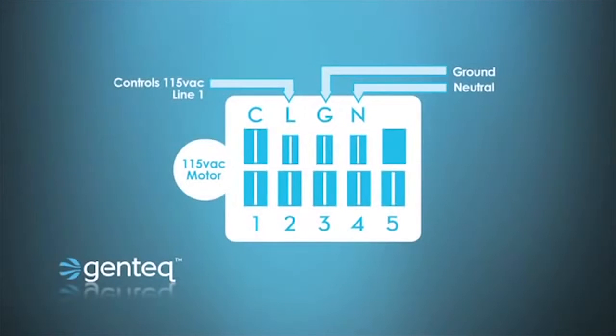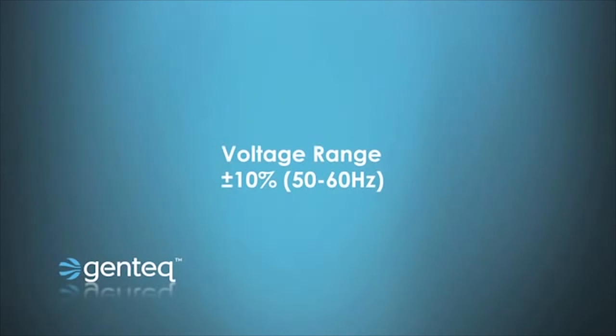On our 115 volt model, the L stands for line 1, the G is ground, and the N would be neutral. On our 230 volt model, the L is still line 1, G is still ground, but in this case, N would be your line 2. Now in both cases, the voltage input to the motor can be plus or minus 10%, and these motors will work on both 50 and 60 hertz power.